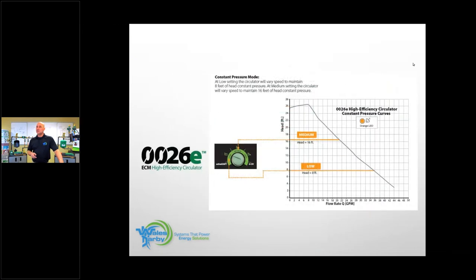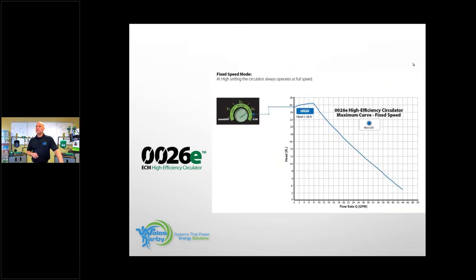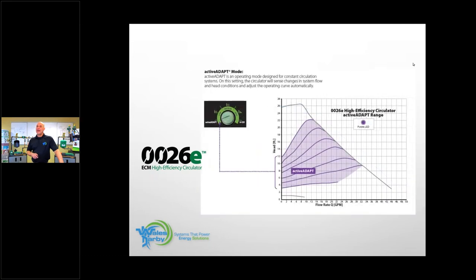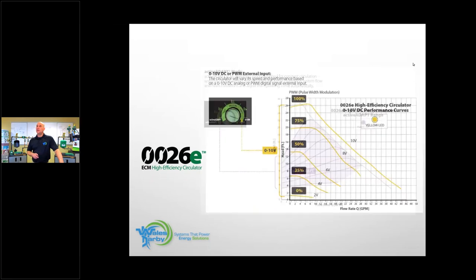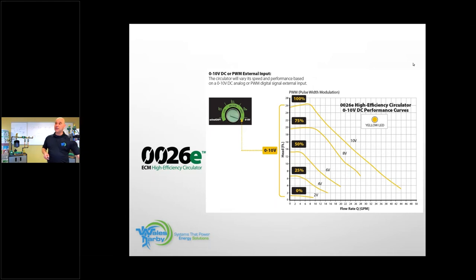And this is just a circulator curve for constant pressure mode. All right, this is fixed speed mode. This is what active adapt would look like. And again, it will adjust itself. And then here, if you have a 0-10 volt DC input, that's how it will work.